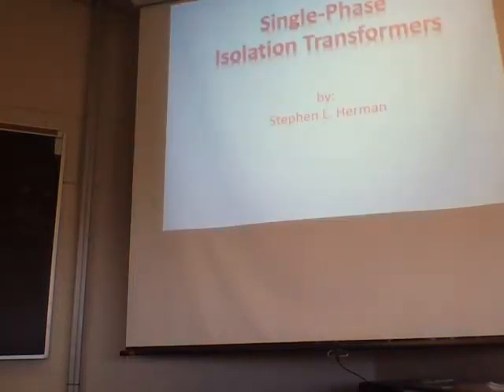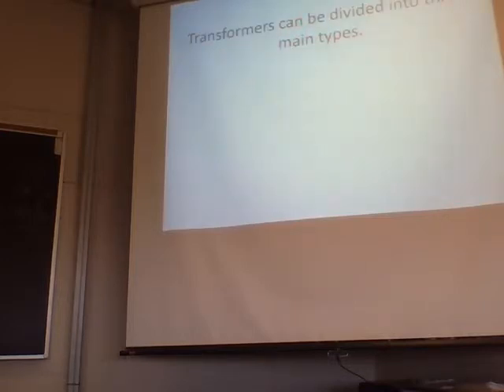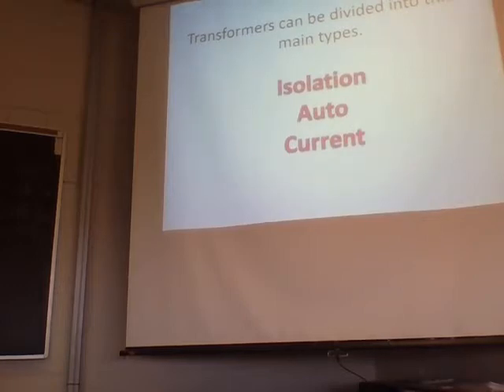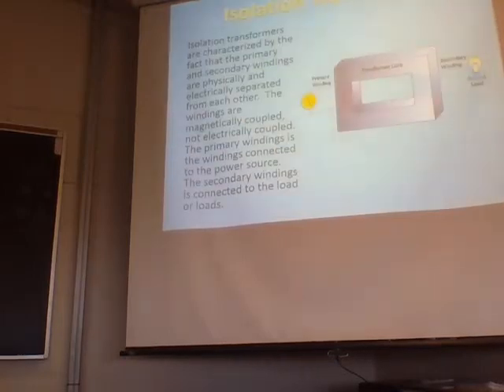So another way of looking at it, transformers can be divided into three types: isolation transformers, auto transformers, and current transformers. So what we looked at first, that's an isolation transformer. Isolation transformers are characterized by the fact that the primary and secondary windings are physically and electrically separated from each other. The windings are magnetically coupled, not electrically coupled.